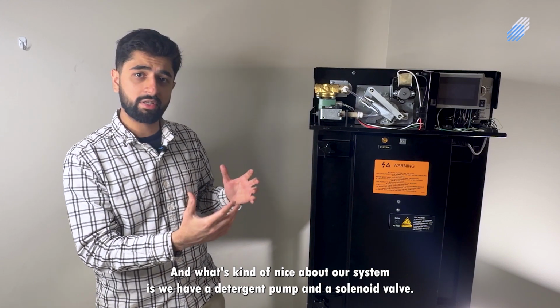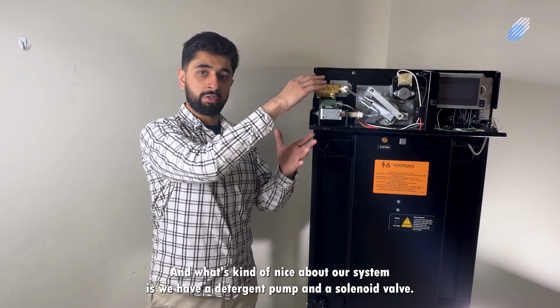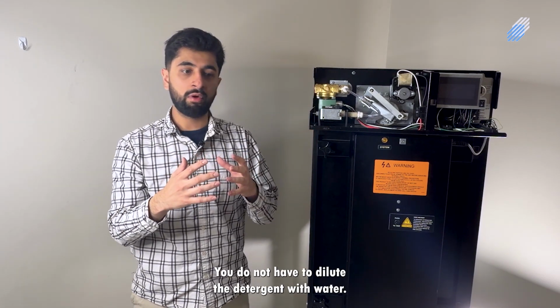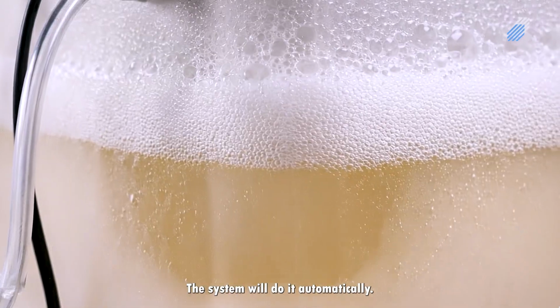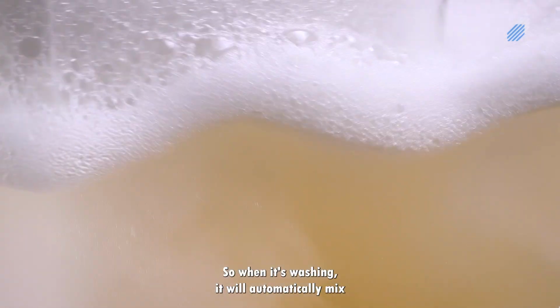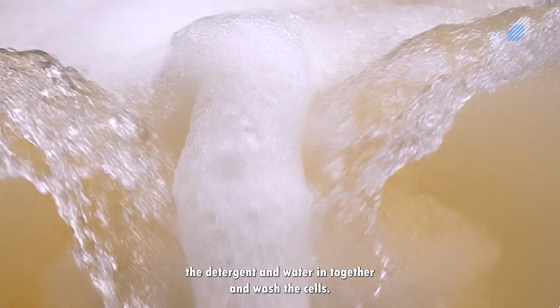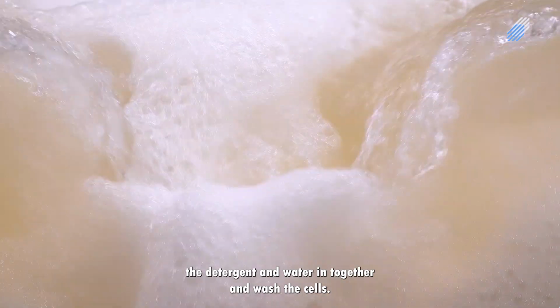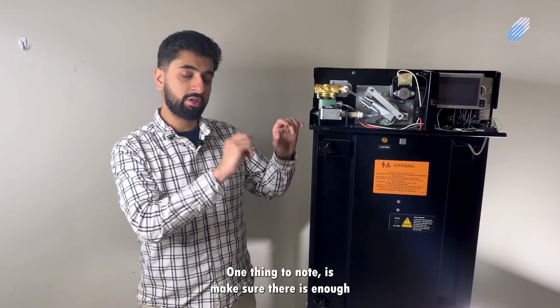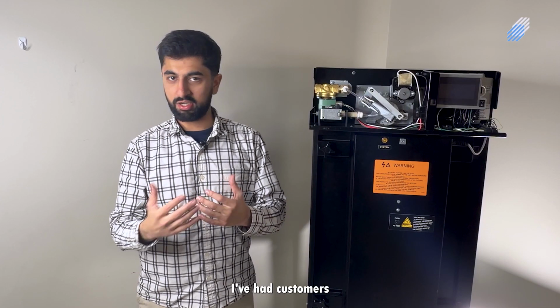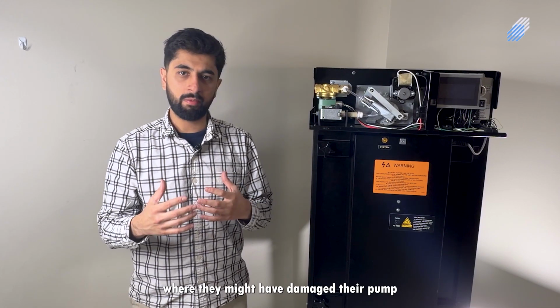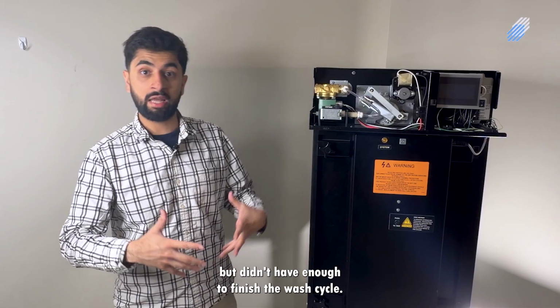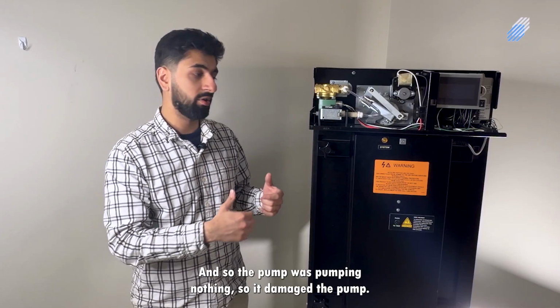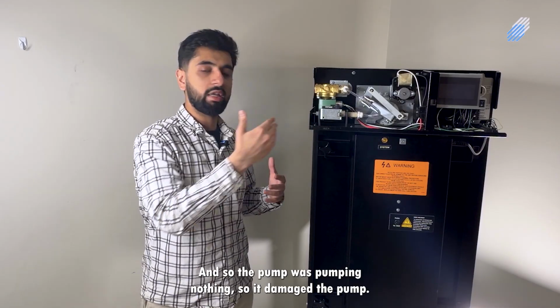What's kind of nice about our system is we have a detergent pump and a solenoid valve. You do not have to dilute the detergent with water. The system will do it automatically. So when it's washing, it will automatically mix the detergent and water together and wash the cells. One thing to note is make sure there is enough detergent in the tank when you start a wash cycle. I've had customers who might have damaged their pump because they had detergent in the beginning but didn't have enough to finish the wash cycle, and so the pump was pumping nothing, so it damaged the pump.